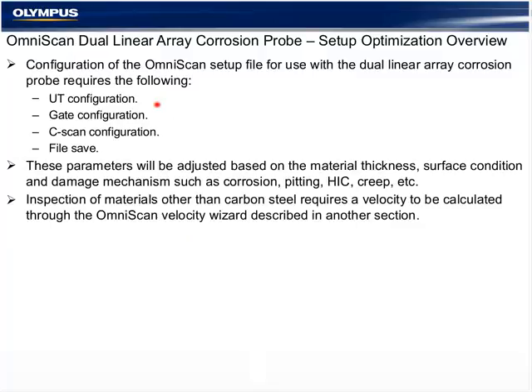The first section for setup, we're going to do the UT configuration, the gate configuration, the C-scan configuration, and file save prior to data acquisition. These parameters will all be adjusted based on the thickness, surface condition, and any different damage mechanism you should be looking for. But for the most part, the overwhelming majority of the applications for this probe are going to be hand scanning for thickness readings and corrosion backwall monitoring. Inspection of materials other than carbon steel requires a velocity to be calculated in the wizard through the OmniScan.